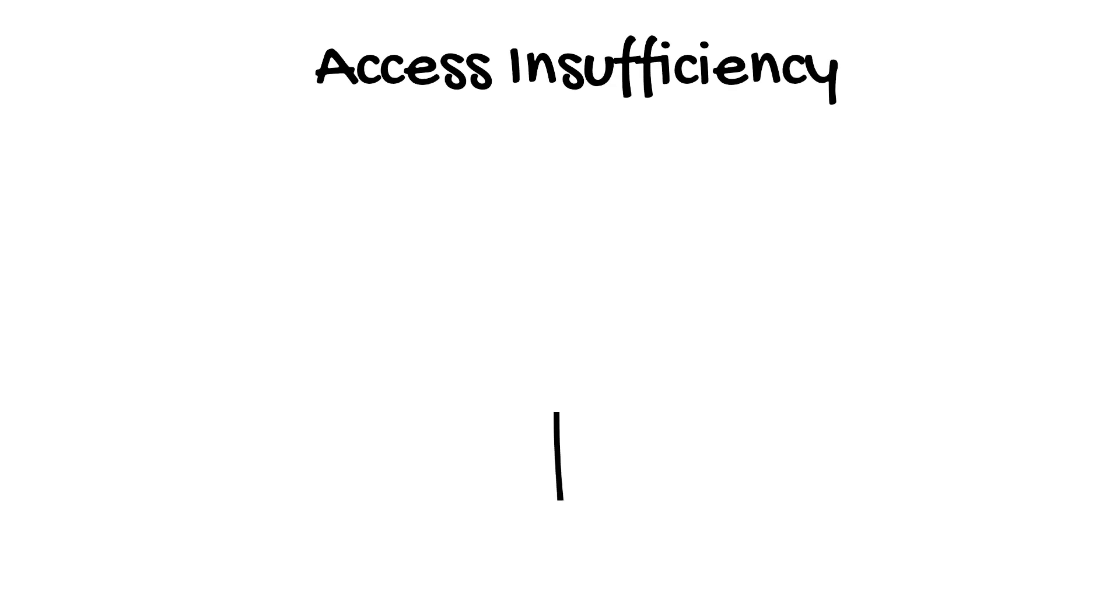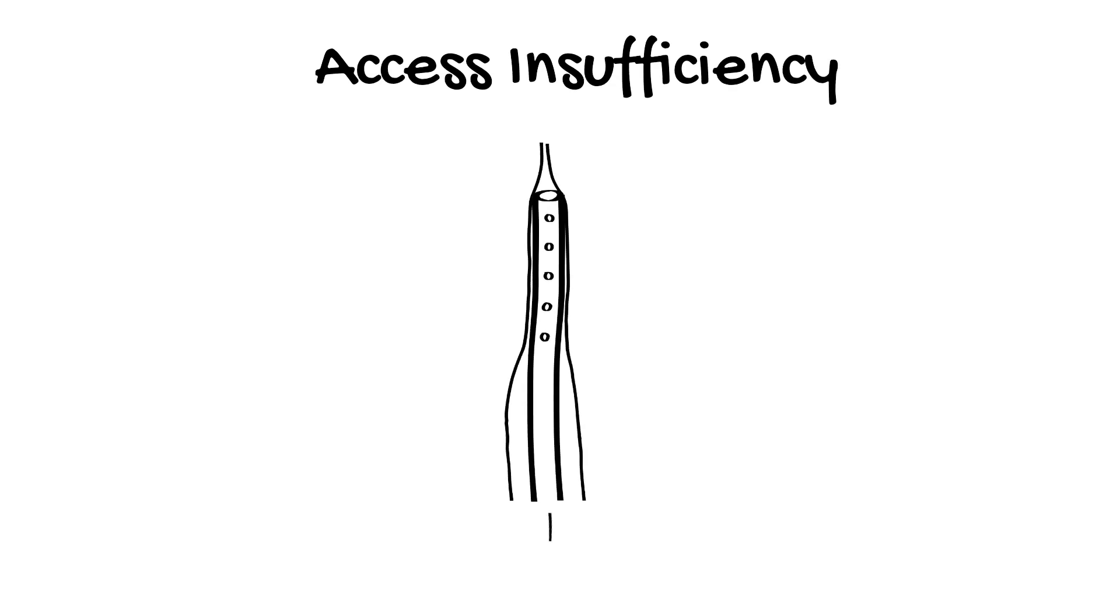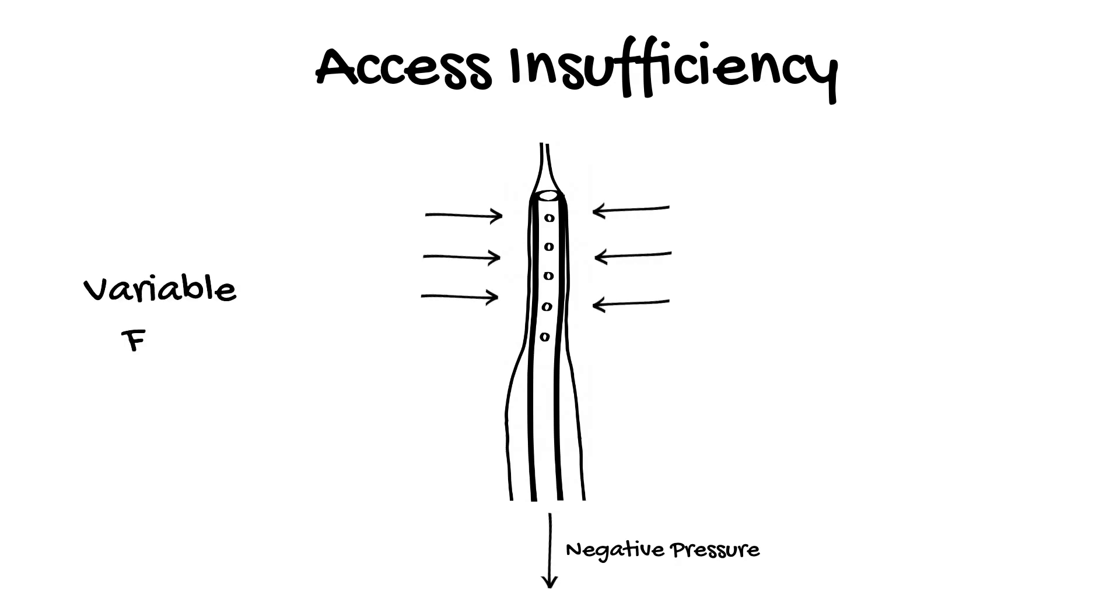Access insufficiency occurs when the negative pressure in the access cannula results in it being sucked up against the vessel wall. This results in variable flow rates in the ECMO circuit, which may drop to zero, and it causes movement in the ECMO circuit, which is often described as chattering.